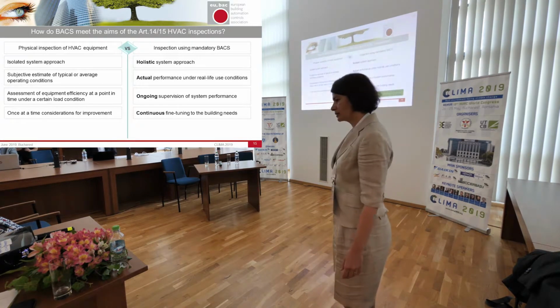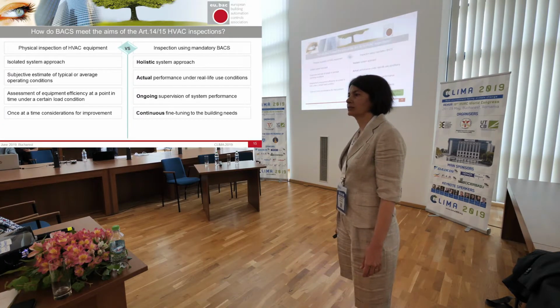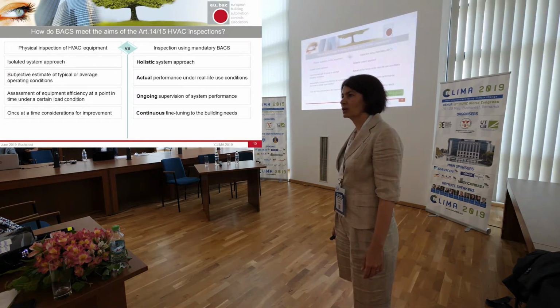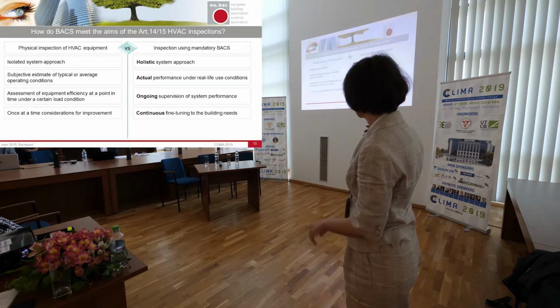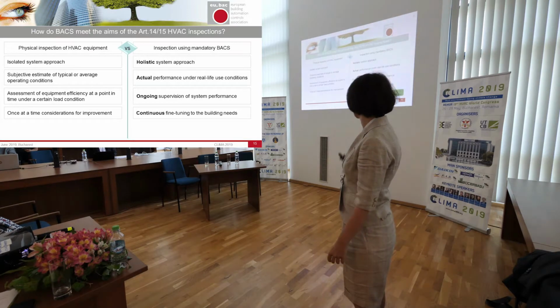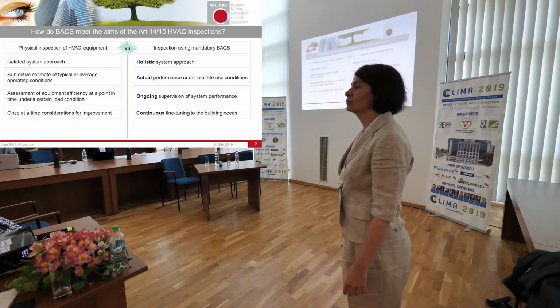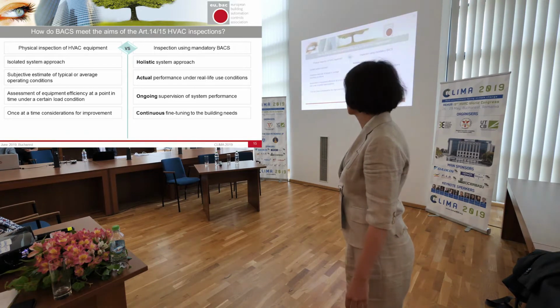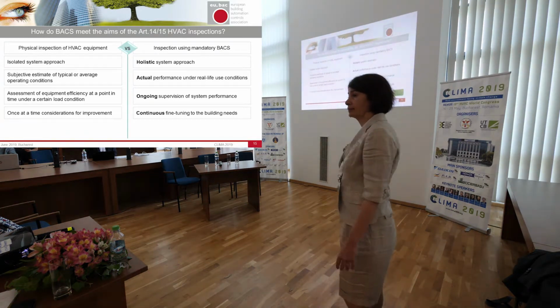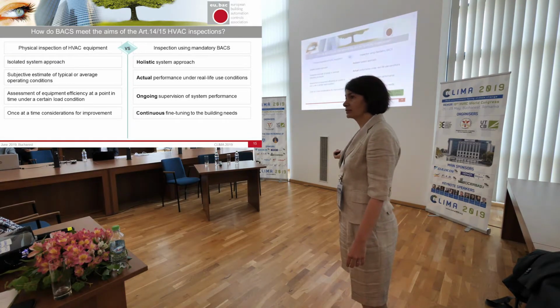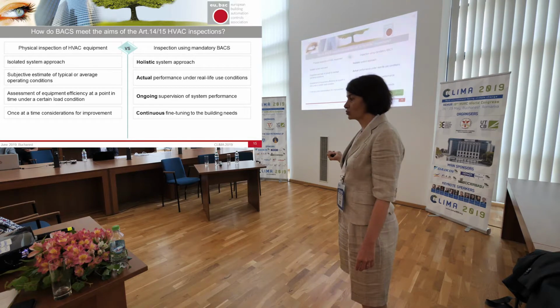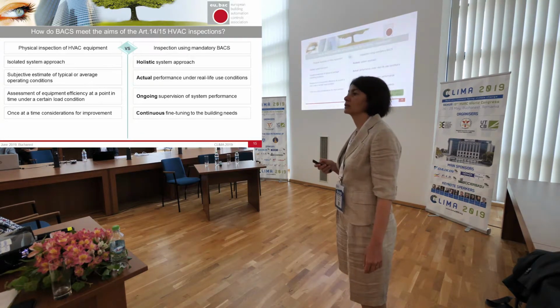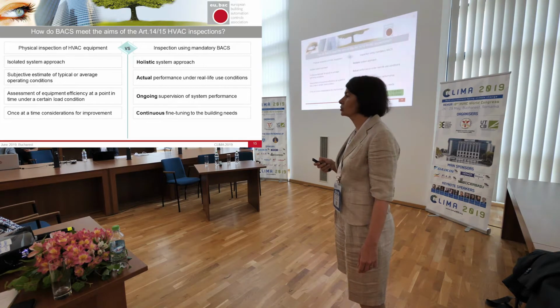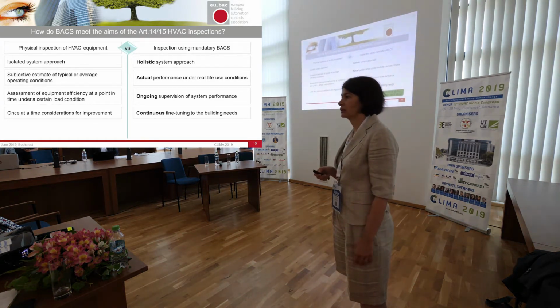One important thing is the impact that has been assessed of actually using building automation systems. If you have a building automation system, the annual energy saving would be up to 20.3% for the whole service sector - this means non-residential buildings. And the return on investment, or the payback, is actually short, between 1 and maximum 3 years. We are talking about buildings with a size of 90 kilowatts and above, so I'm not talking about every little hut in the mountain.